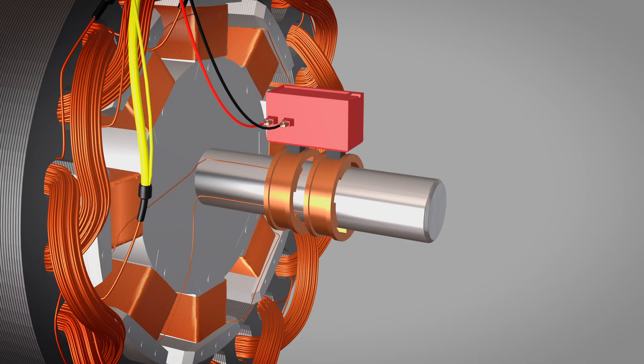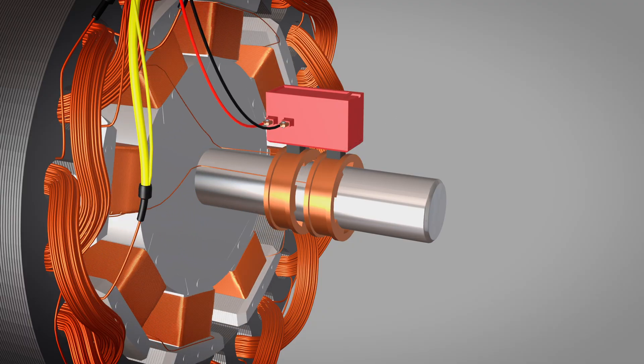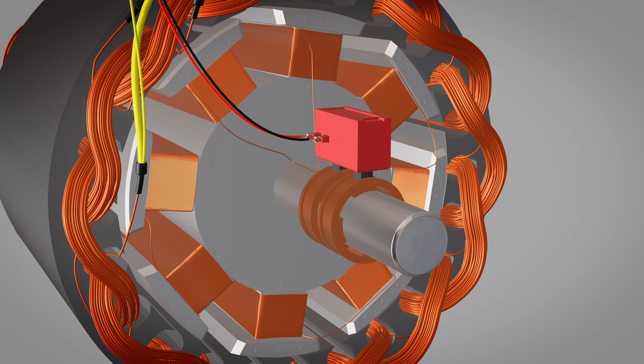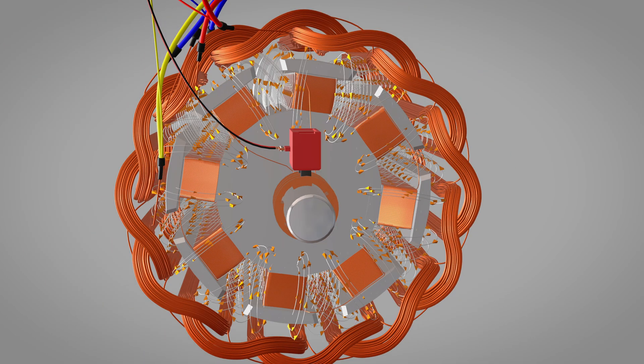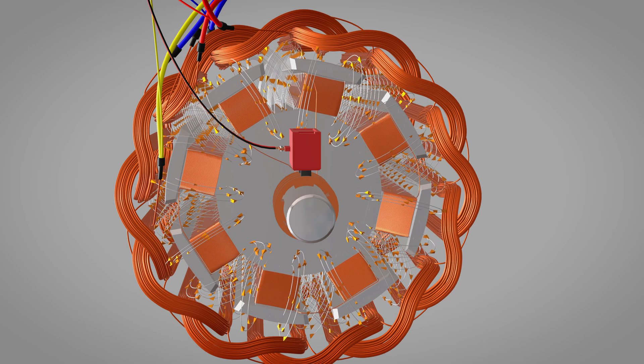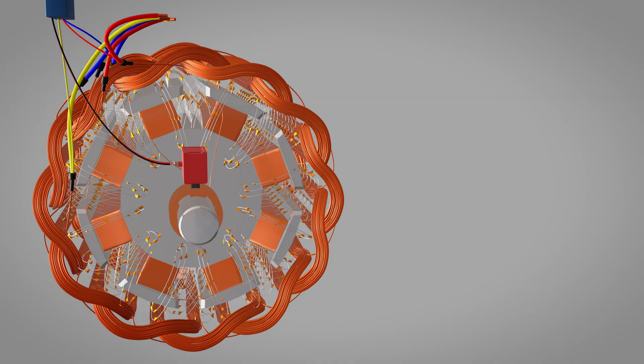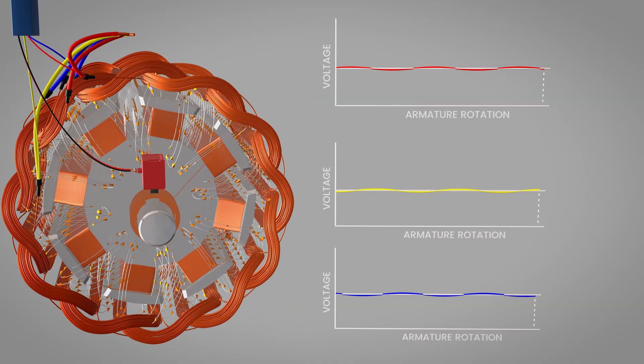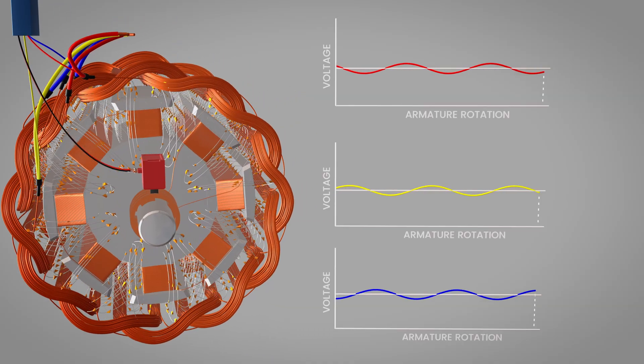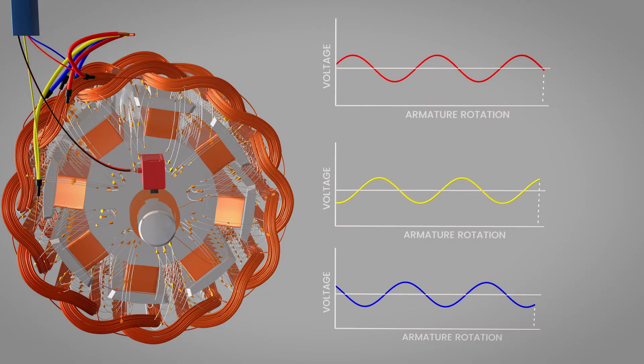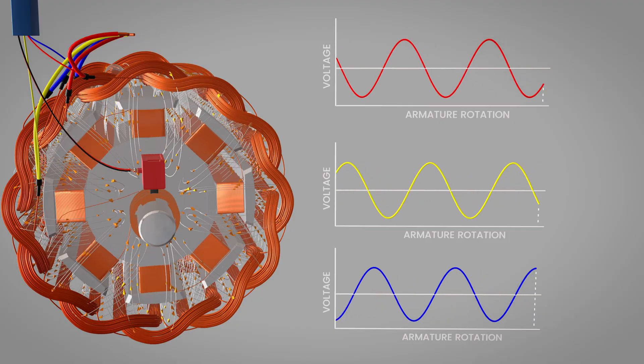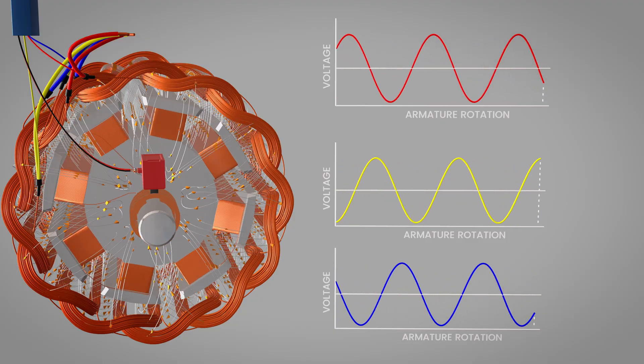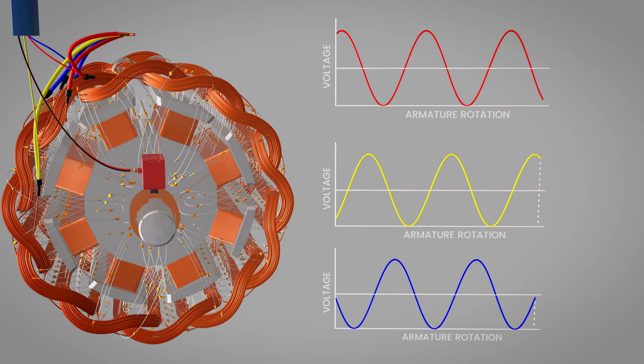Although the system is fully autonomous once running, a unique startup challenge arises. With no external source, the alternator must rely on residual magnetism, a tiny remnant magnetic field in the iron cores of the field windings. When the rotor begins turning, this weak residual field cuts through the stator windings, inducing a small initial voltage. That voltage, though minimal, feeds back through the AVR to the field windings, thereby amplifying the magnetic field. As the field strengthens, the generated voltage increases, creating a bootstrap effect that rapidly builds to full-rated voltage.